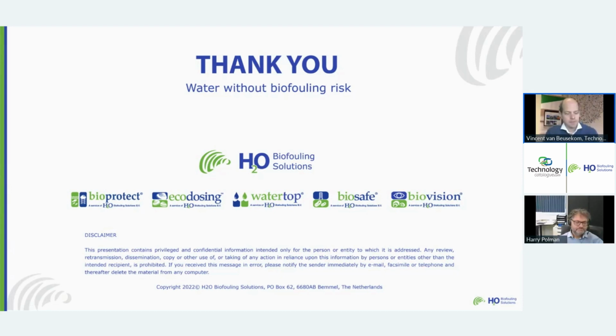Another question, more related to applicability: is ecodosing also suitable for closed cooling systems, like biofilm in paper mills? I think yes. However, to prevent biofilms in closed cooling tower systems, you need much less biocide dosing over a much shorter period. The biofilm probe shown in the slide measures the buildup of biofilm, and using it you can tune your biocide dosing to an absolute minimum — generally required for between 15 minutes and 1 hour a day, which should be sufficient to prevent any buildup of biofouling or biofilms.